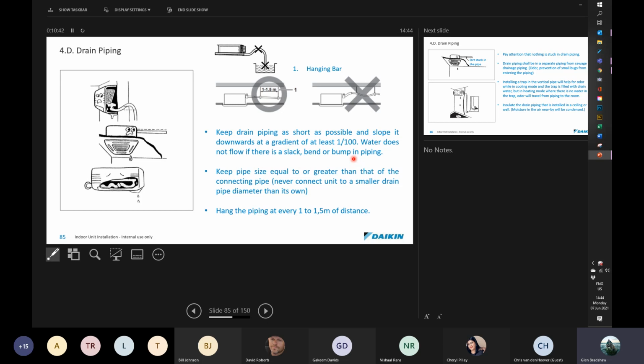And the easiest way to get this is a bit of fishing line tied onto a bracket and a spirit level, and you just drop the spirit level down until you get one bubble, which is that first line flowing away from the unit, and that'll give you sufficient flow away from the unit. Okay, pipe hanging should be every 1 to 1.5 meters.